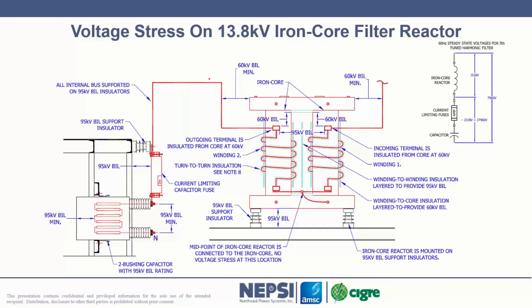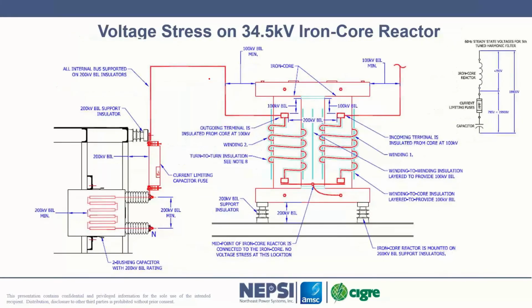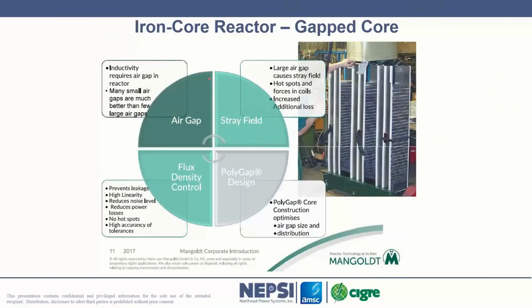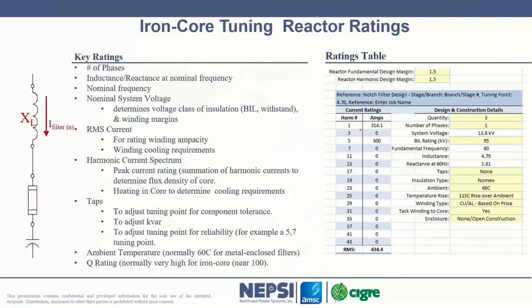So voltage stress is in a typical iron core design. Again, you can go back to watch the video, see what this is all about, but we're able to distribute the voltage in the system and improve the reliability of the harmonic filter by using a floating core design. And we show the same thing at 34.5 kV, so 2 different voltage levels. This is a stacked core design from a very good reactor manufacturer, and what you see here is all the gaps that are being used, a significant number of gaps. This is how the inductance is created in an iron core reactor, and it's also very complex, and that's why there are only a few suppliers out there that can properly do it.